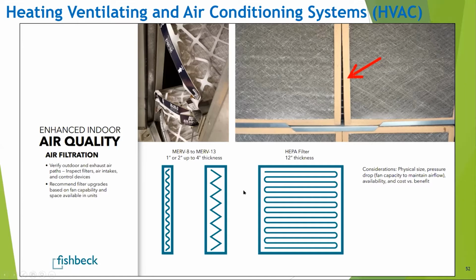And there are some restrictions in terms of both the physical space that's available in the equipment to fit a larger or a thicker filter. And there's also limits of how much the capacity of a fan to move air through a more dense filter. So the denser the filter, the less airflow you get. And at a certain point, you significantly reduce the airflow if you try to increase the density of the filter. And this can cause, for instance, this filter here is collapsed and there's gaps. And so they're looking at all of these things around our filters and providing us recommendations on a case-by-case, building-by-building evaluation.